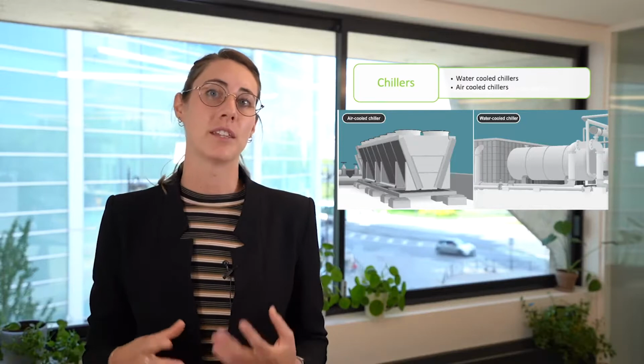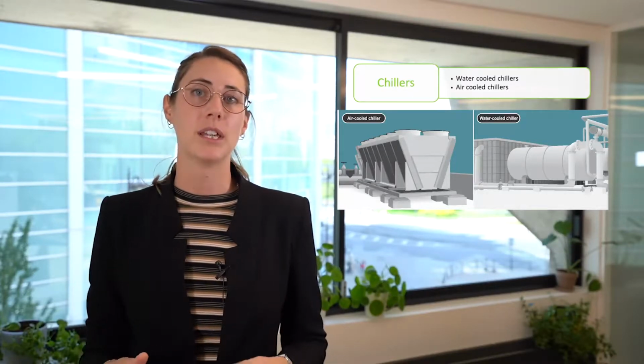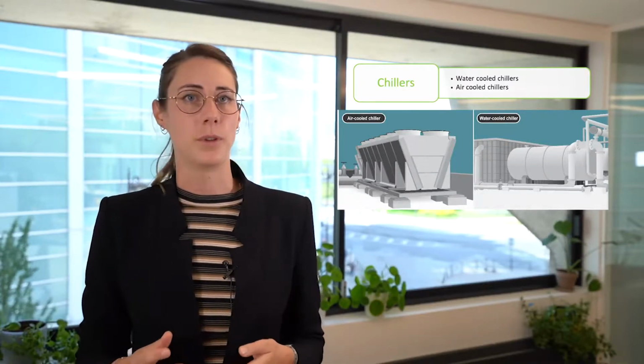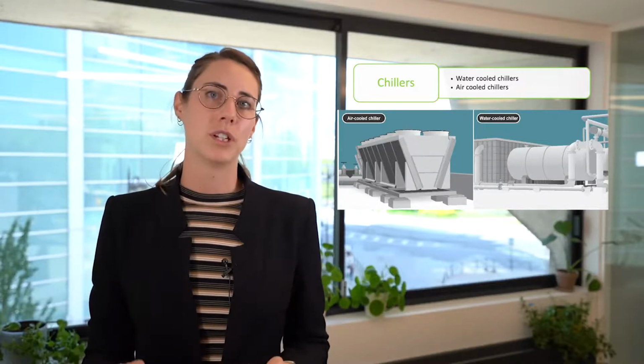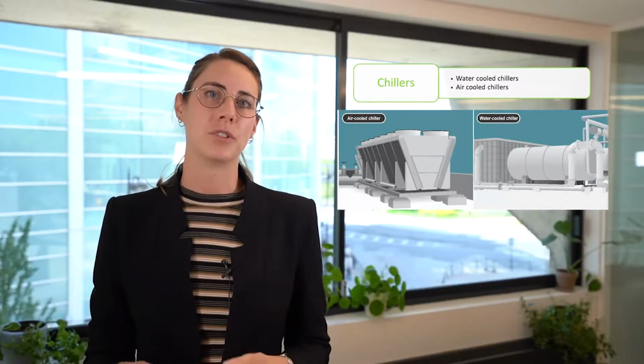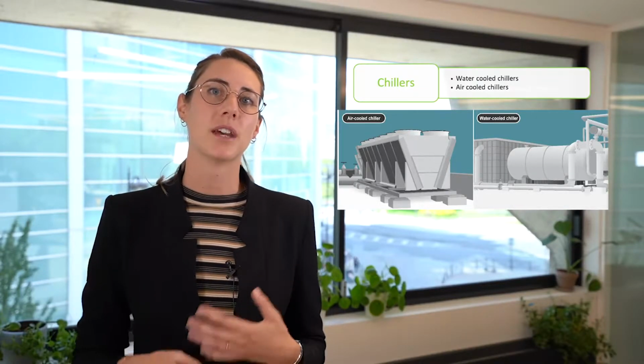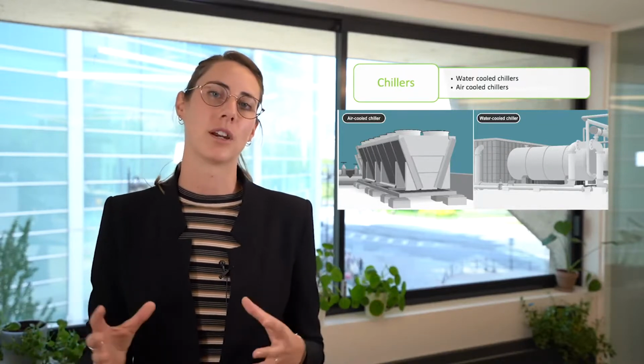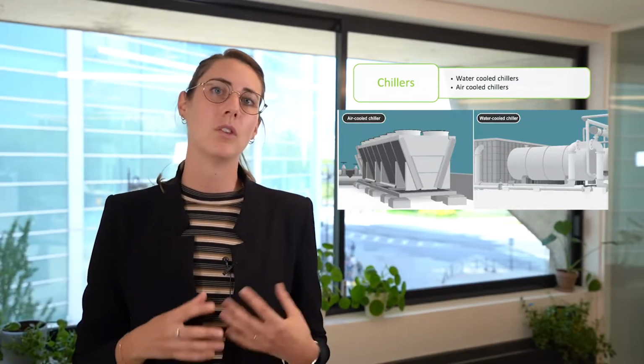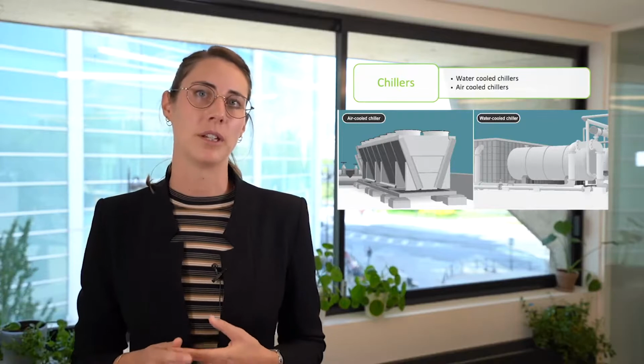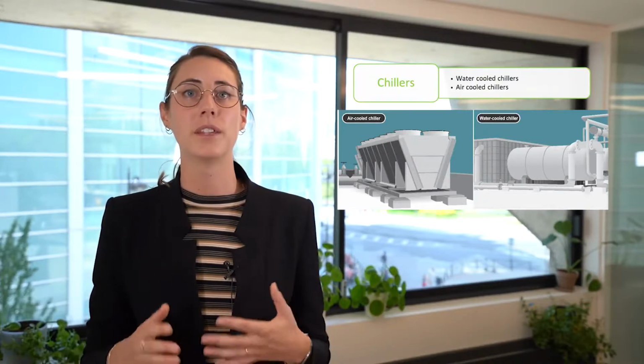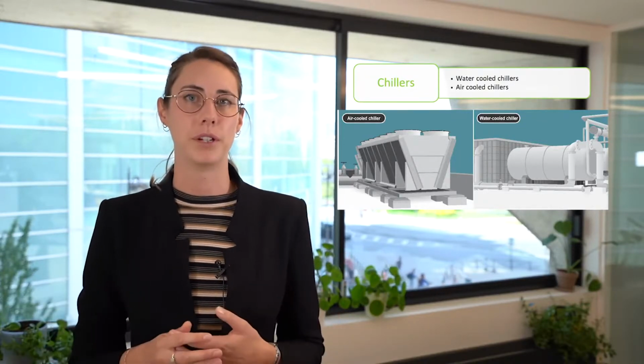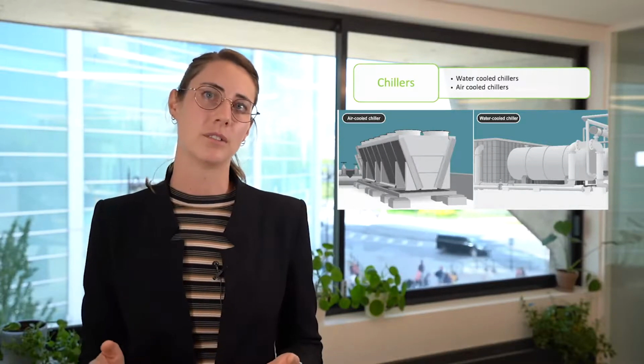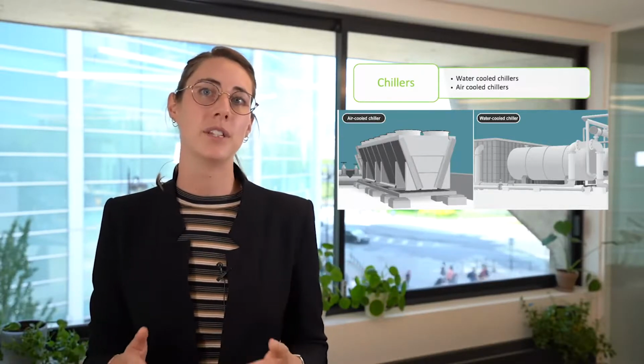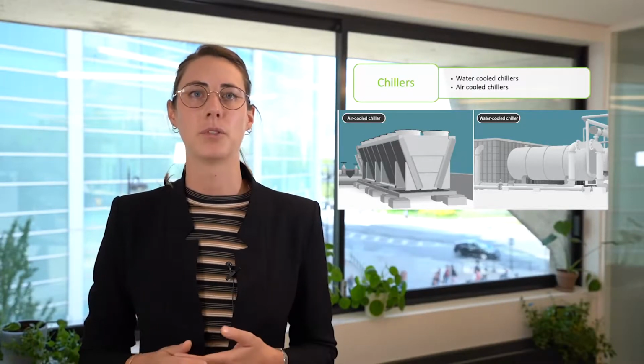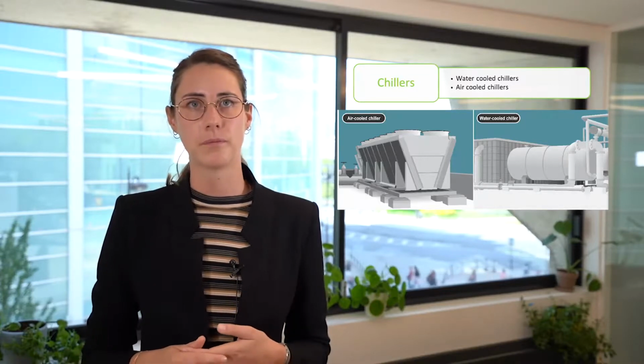Chillers have to reject the heat they extract from the building, either to water or to air. Water-cooled chillers use a condenser and refrigerant to reject heat to the water, getting the water to absorb the heat extracted from the building. The water is then pumped to a cooling tower and circulated using fins to expel the heat to the atmosphere, typically through evaporation. In certain cases, cooling towers can be replaced by ground heat exchangers, which can reduce the amount of water to be evaporated.